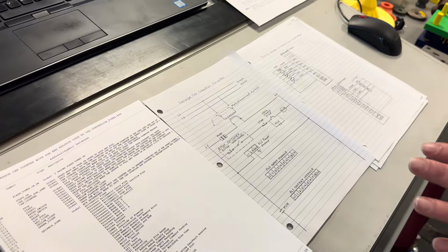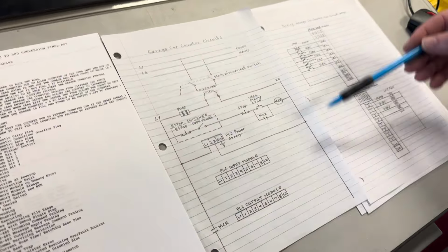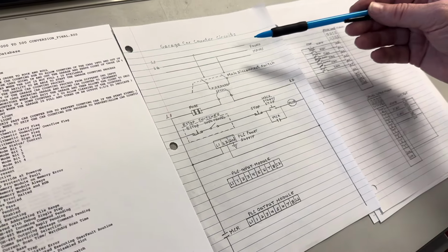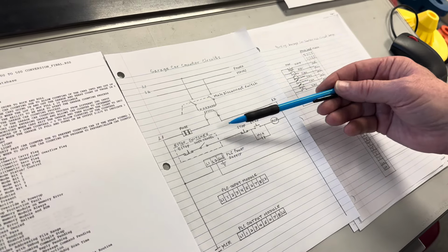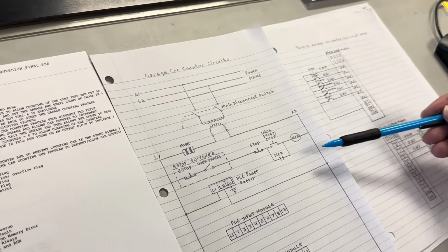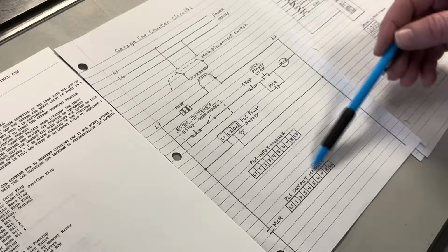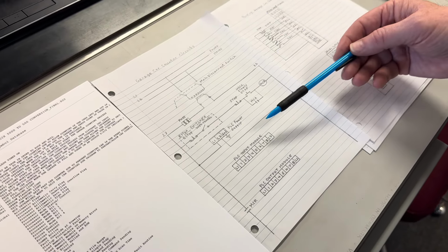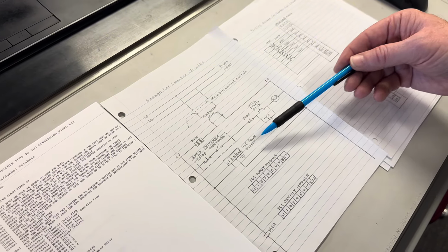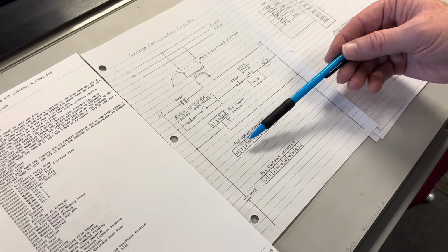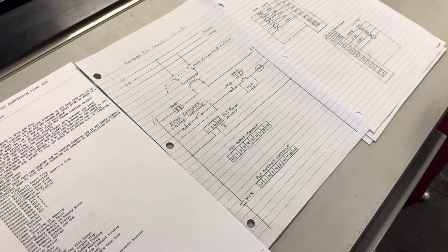Now those inputs and outputs are hardwired, as you see right here. This is the general powering of the circuits. We have our main power coming in, going down through our e-stop switches, main start, the main master control relay, controlling whether these will be scanned or not, operational or not, I should say. And you can see that the PLC power supply is below that with our PLC input module, and then our PLC output modules. The MCR is just below that.